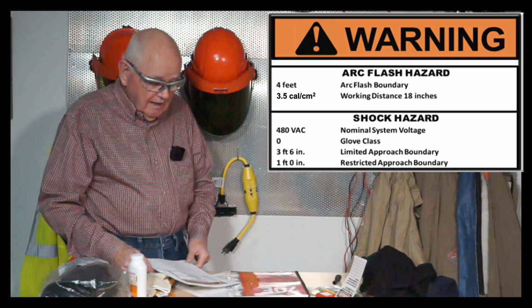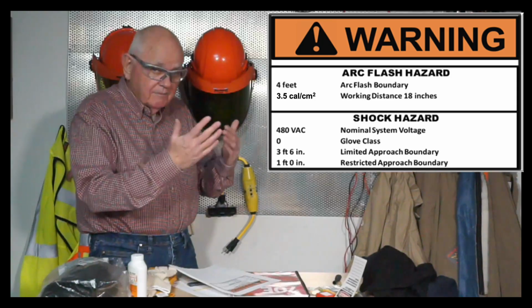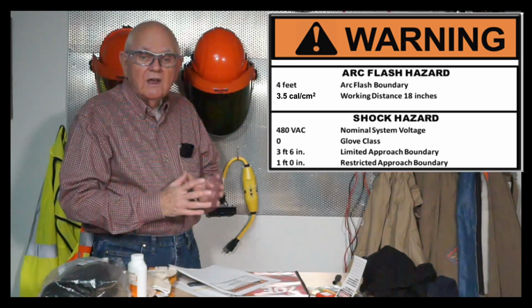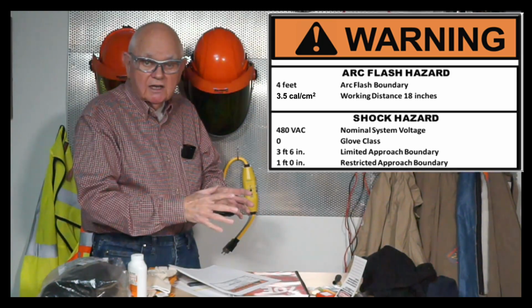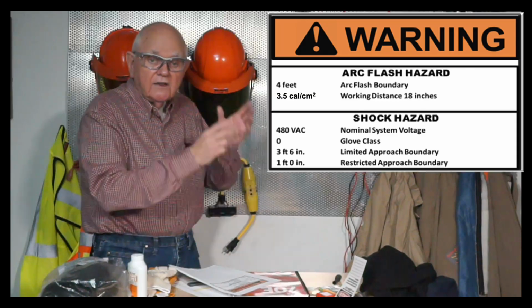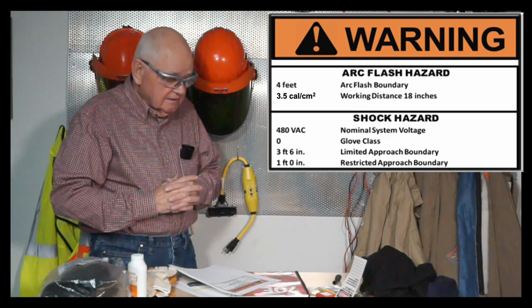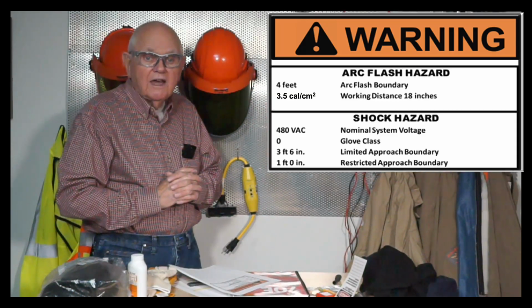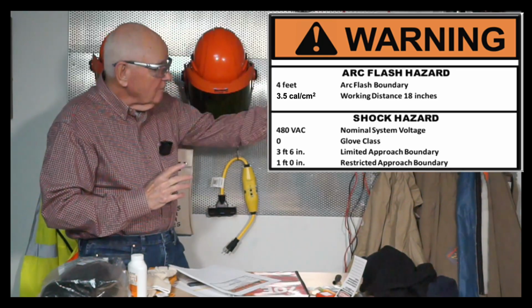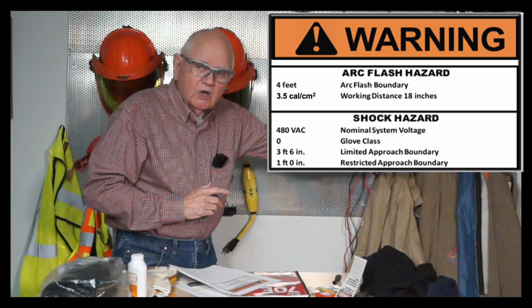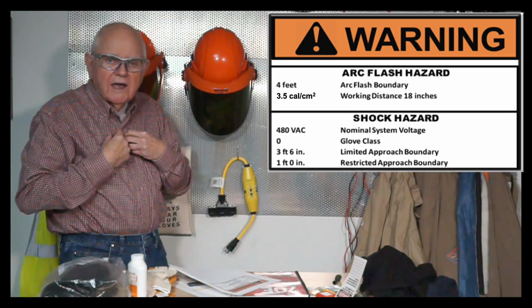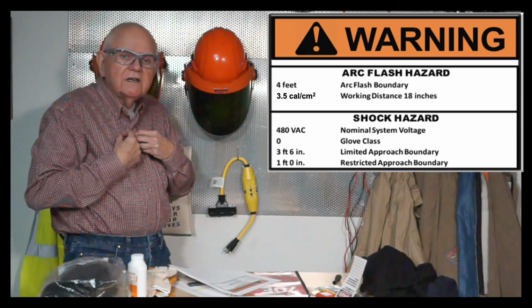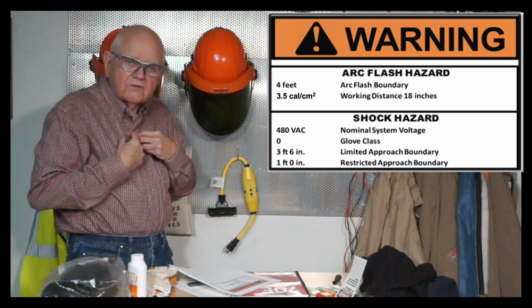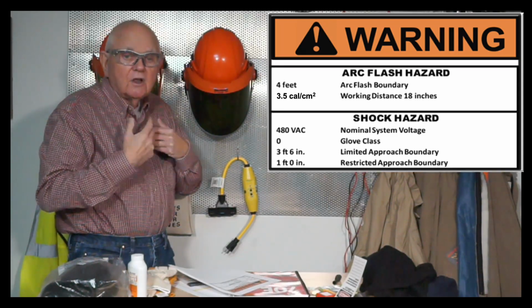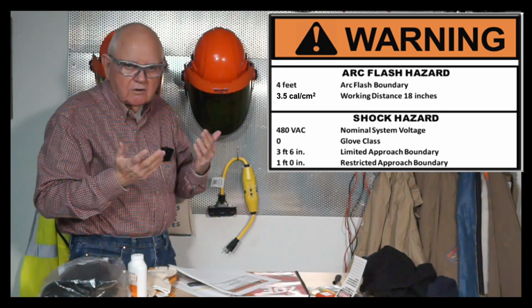Now, this particular label is divided up, as most are, into two separate areas. I have an arc flash hazard and I have a shock hazard. The arc flash hazard tells me that there's a 4-foot arc flash boundary. That means if I'm going to have an arc flash over here and I'm 4 feet away, that's where the incident energy is going to drop to 1.2 calories per square centimeter, which is the onset of a second-degree burn.